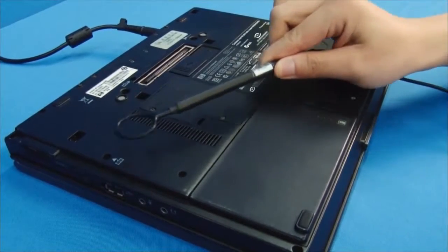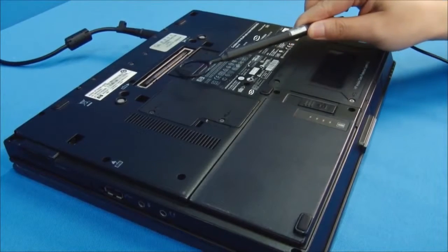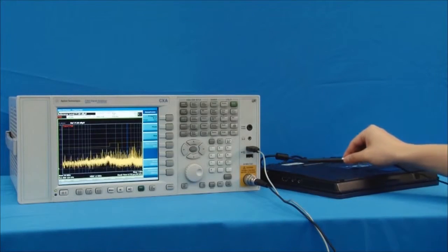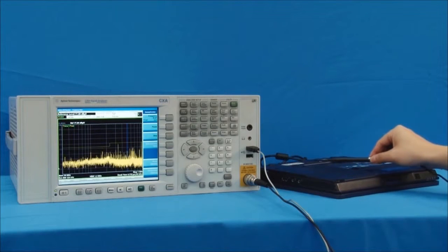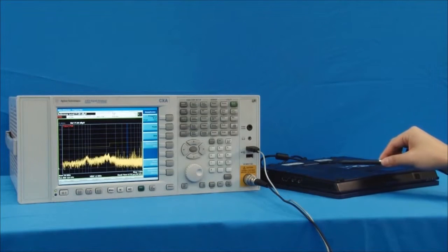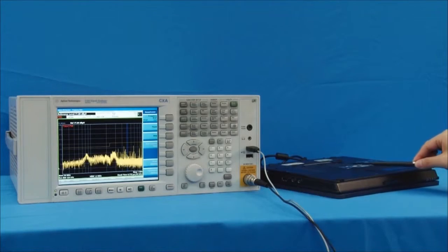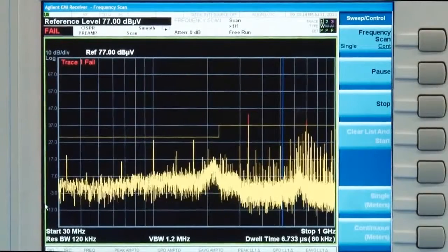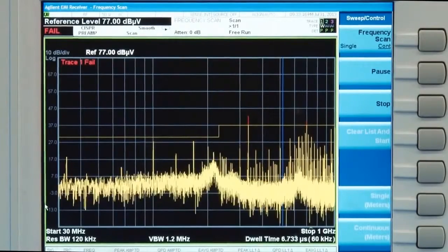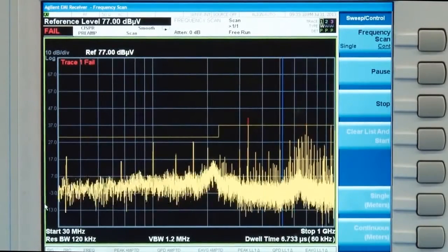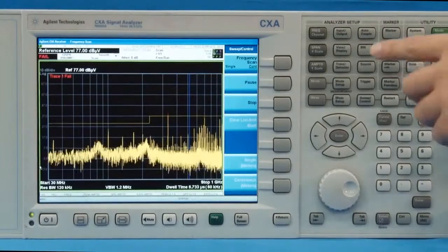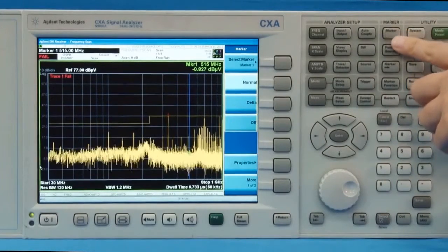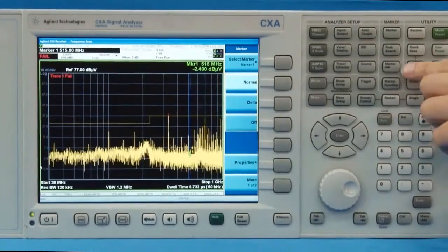We move the probe over the back of the notebook at a distance around 2 cm. On the display of the spectrum analyzer, we see the signals which are radiating from the DUT. The signals may vary when we move the probe. We notice there is an obvious signal with high amplitude. To locate the source of emission, we place a marker onto that signal — its frequency is about 333 MHz.